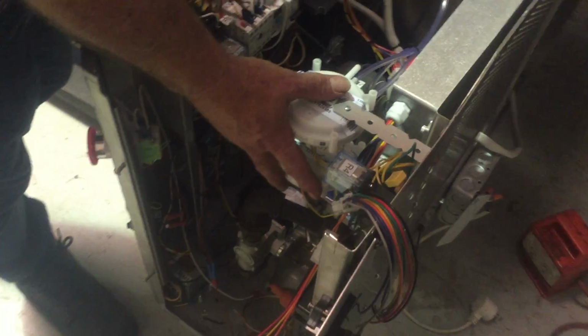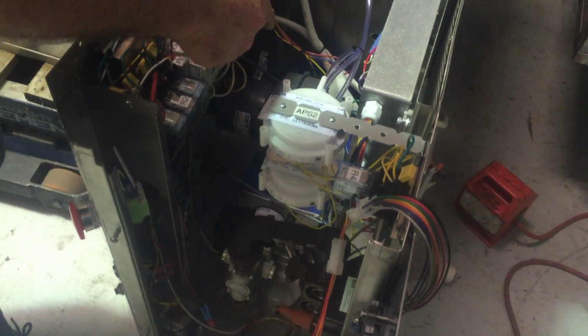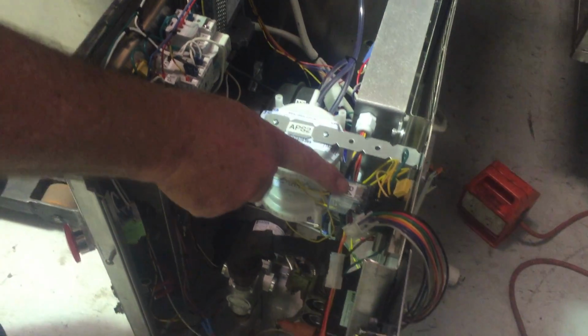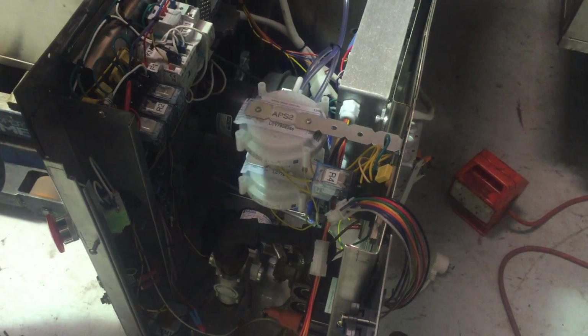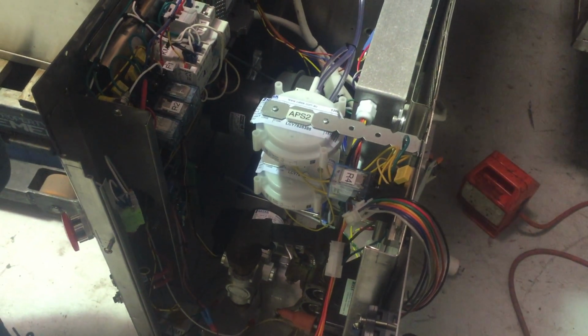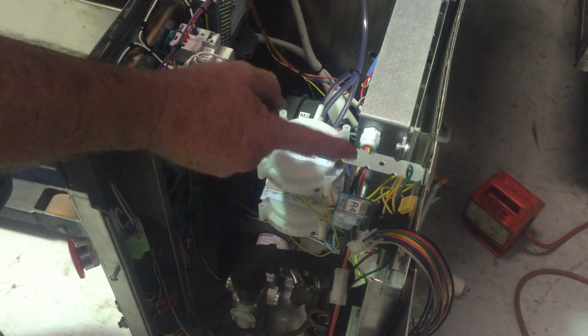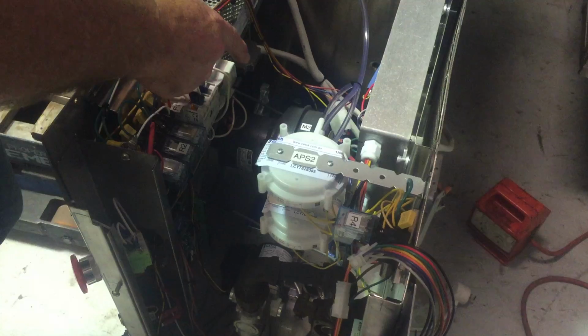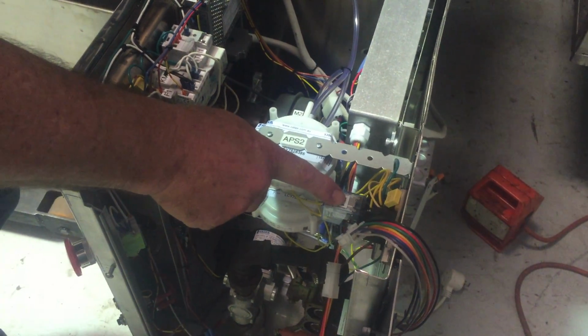New air pressure switches. The blower motor has got an interlock relay, which adds to the safety. So the interlock relay has to see that in the off position before it starts. If that's running for whatever reason, then that will lock out and you won't be able to use it.